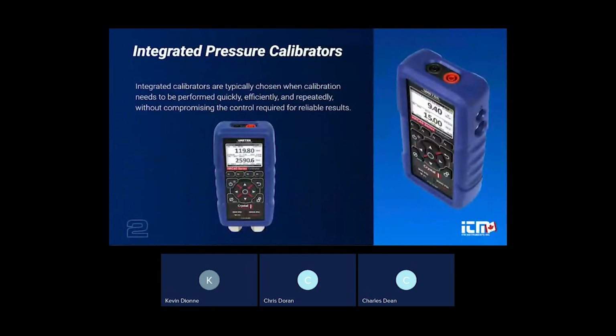In practice, the choice between a pump gauge setup and an integrated calibrator often comes down to workflow rather than accuracy. Integrated pressure calibrators are well suited for situations where speed and efficiency are priorities. Because pressure generation and measurement are combined into a single device, your setup time is reduced with fewer components. Like in that kit you saw, there aren't a bunch, but there are different components that go into it. Using an integrated calibrator brings it all into one, which minimizes your potential for error and your potential for leak points. It improves your ability to move quickly between test points. Pressure can be applied, adjusted, and held with minimal interruption. Overall, they lead to a smoother and faster result during your calibration process.